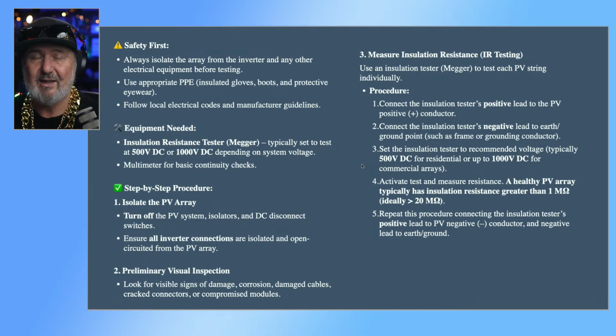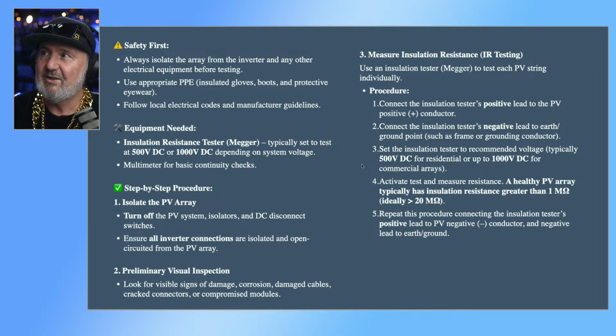Now, last week we covered a case study on a system where the plug and sockets had failed and there were burning holes in the roof from arcing. So then go and measure the resistance. So test each string. You're going to test between positive and earth and negative and earth, presuming it's a floating array.